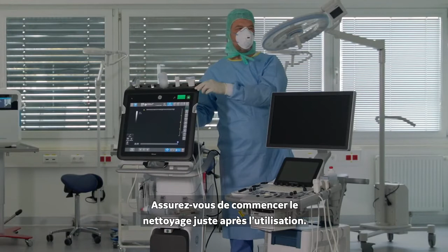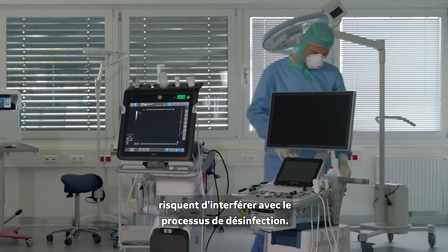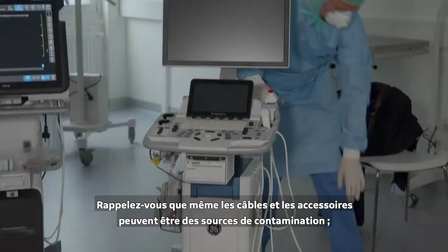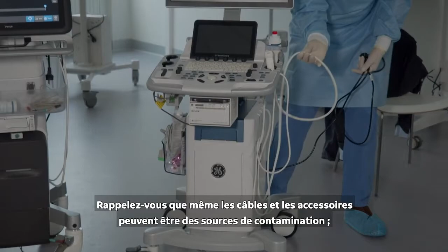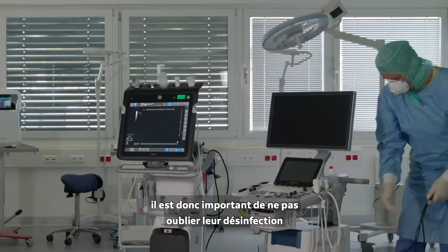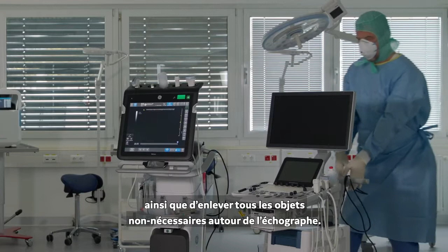Make sure to begin cleaning immediately after use. Drying and adherence of biological debris may interfere with disinfection later. Keep in mind that even cables and accessories can become sources of contamination, so it's important not to skip their disinfection as well, and to remove any unnecessary objects from the ultrasound machine before getting to the patient.